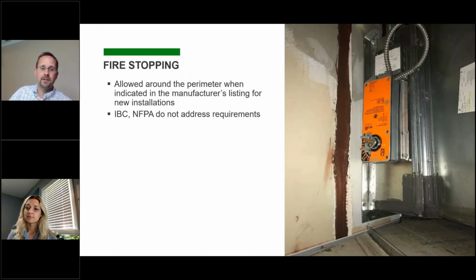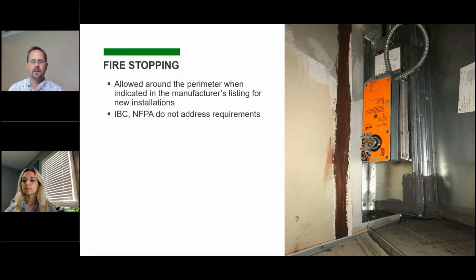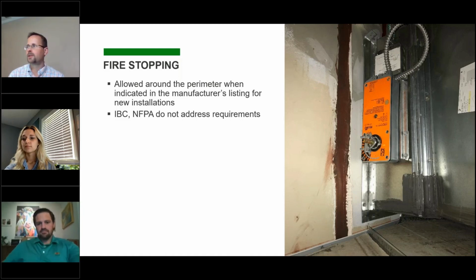So the last thing I want to talk about is fire stopping. There's a lot of options, and over the last 5+ years, there have been options for increased space, instead of having retaining angle on both sides, options for one side retaining angle, or allowing fire stopping around the perimeter on one or both sides to minimize the installation cost, but also make it easier to install in certain tight scenarios. The codes don't quite refer to this, and that's why it's important to look at the UL listing and, if you're going to do something different, apply it specifically how the UL listing requires.